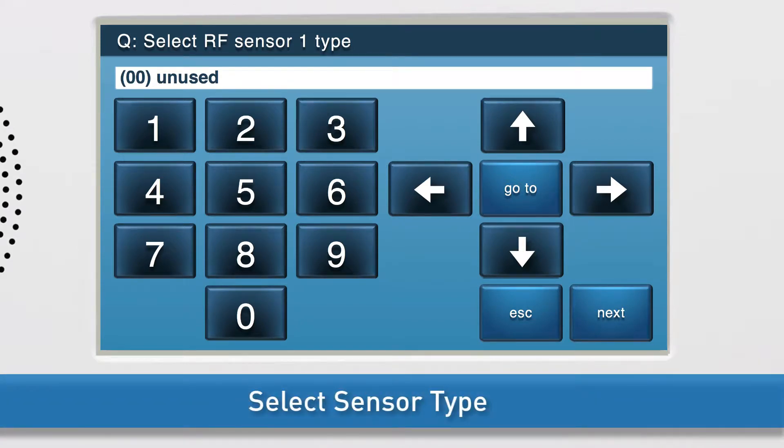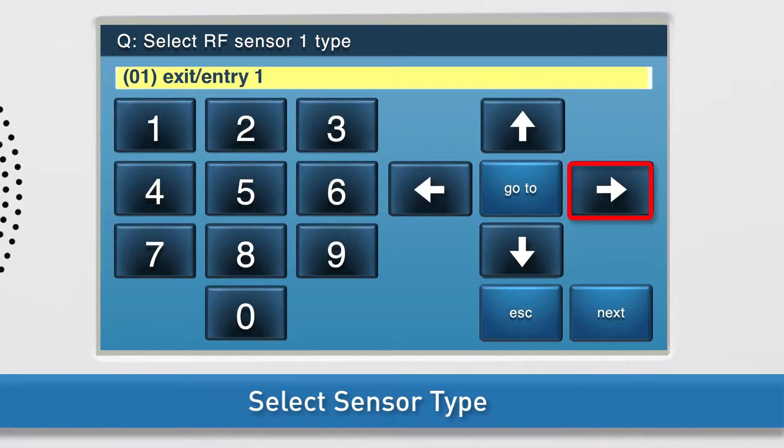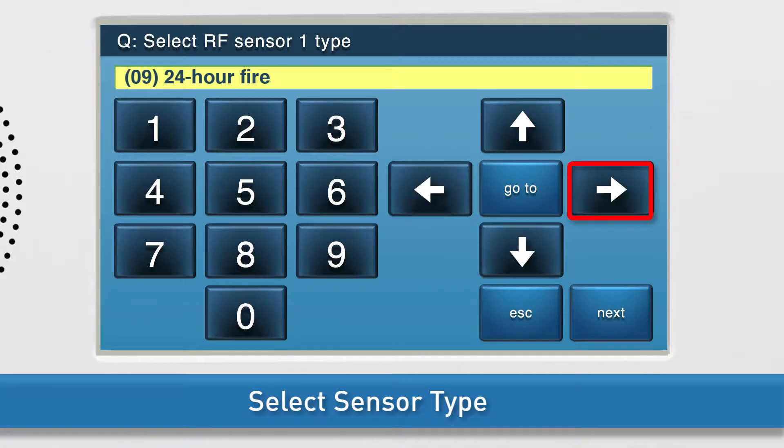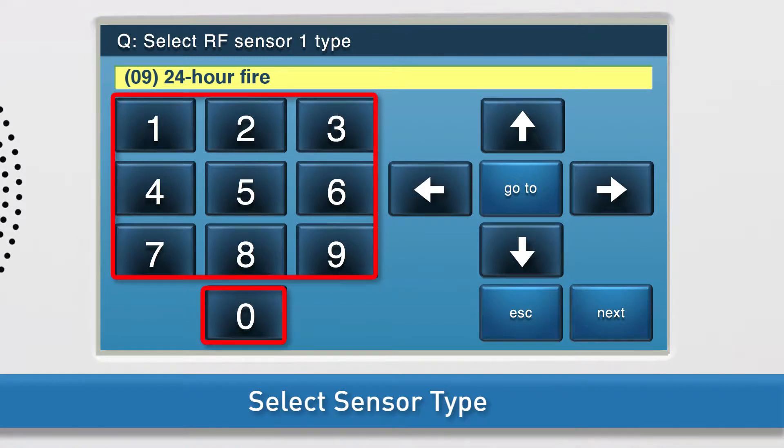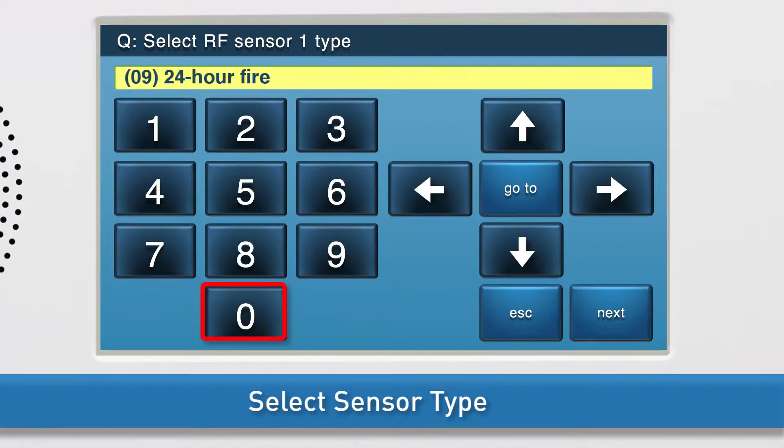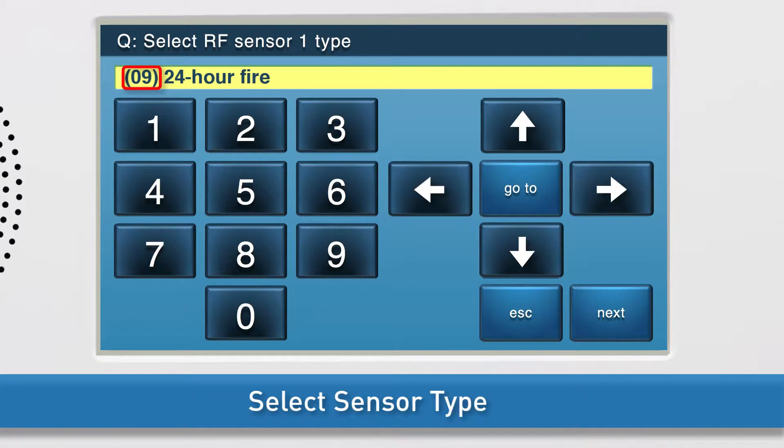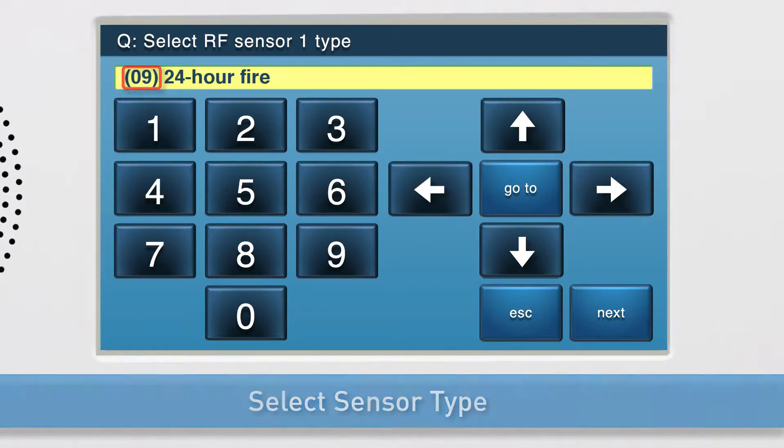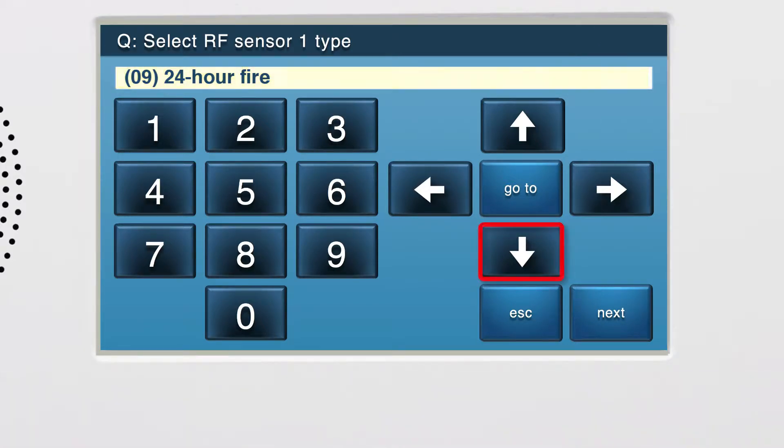Select the sensor type. There are two ways to change the sensor type. Option 1: Press the right arrow until 24-hour fire displays on screen. Option 2: Use the on-screen keypad to type 09, which is the two-digit code for the 24-hour fire sensor type. Press the down arrow to go to the next sub-question.